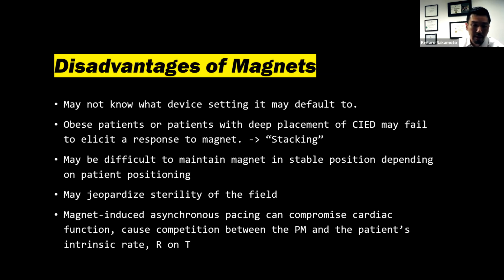Also, it may jeopardize the sterility of the field, and magnet-induced asynchronous pacing can compromise cardiac function depending on the patient, causing competition between the pacemaker and the patient's intrinsic rate, and causing things like R-on-T phenomenon, which can result in a fatal arrhythmia.